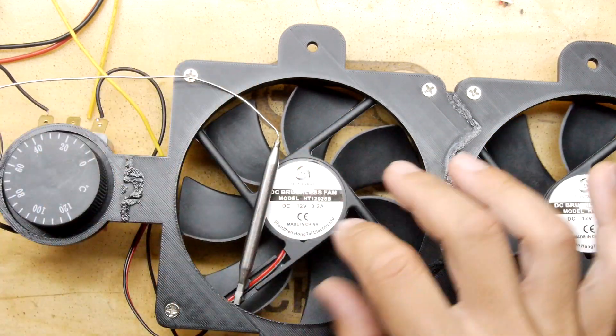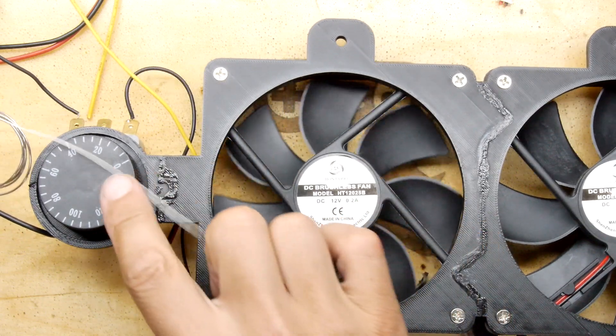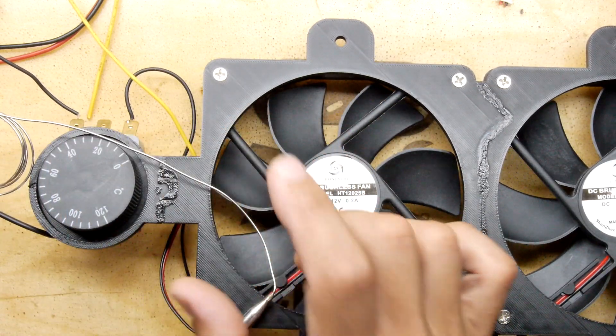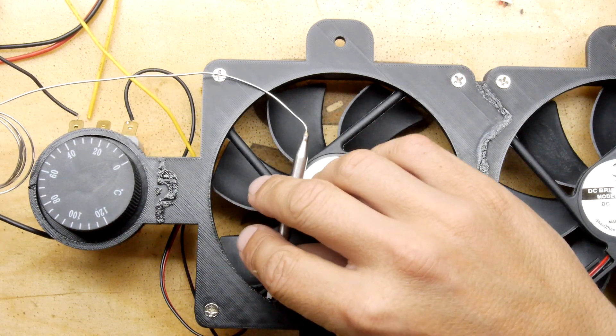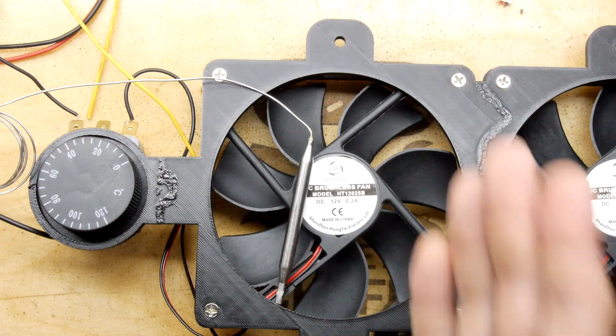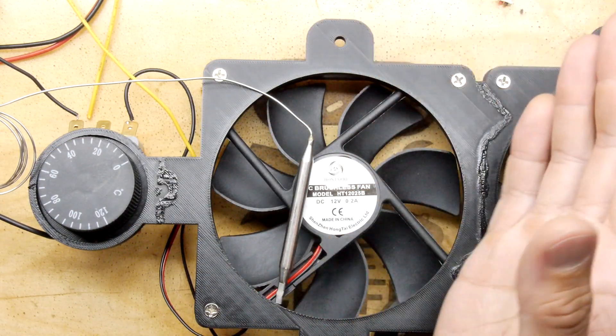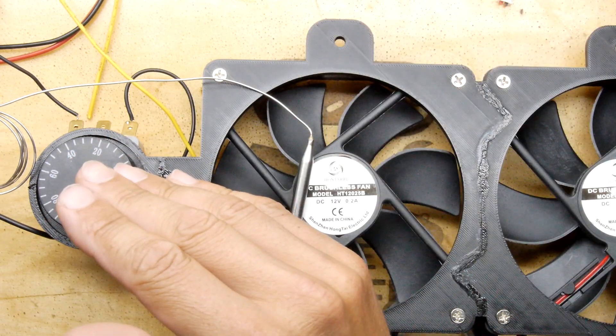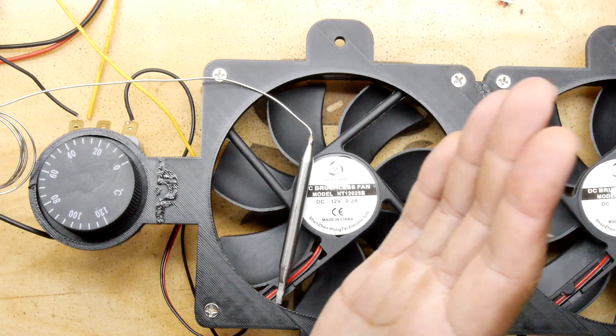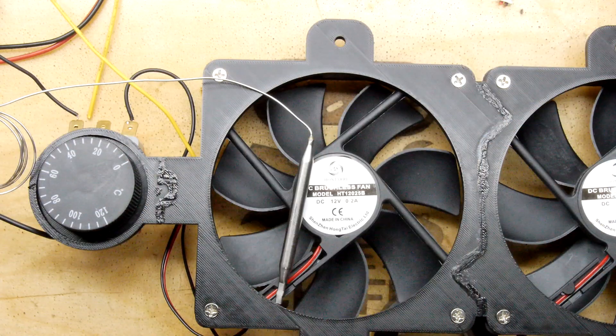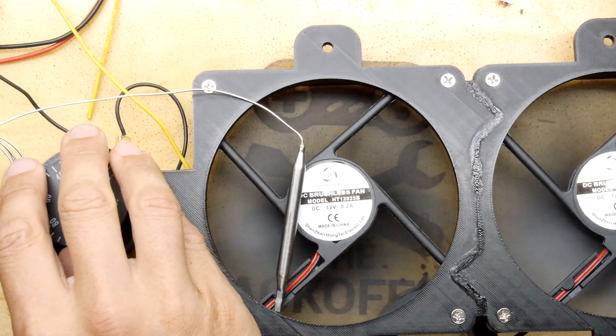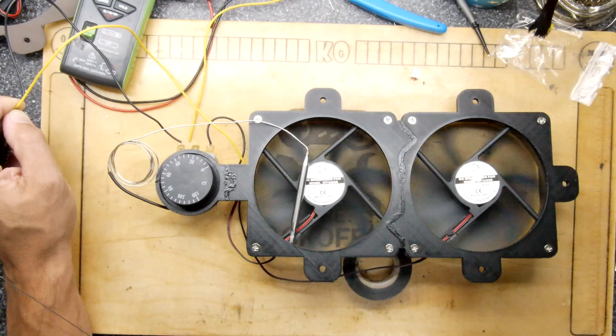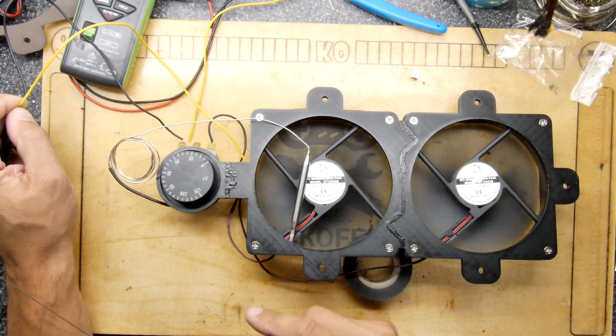Oh there's way too much hysteresis in this for it to do that. It'll do it if it's a digital one, but even then you'd have digital hysteresis. Hysteresis means that it will go either side of the set temperature for a fair bit so that the thing isn't switching on and off constantly. The switch isn't going on off on off on off. It'll have to, for example if you set it to 20 degrees, it might take up to 23 degrees before it turns on and then it might take down to say 17 degrees before it turns off, so it's always floating around that median set point either way.